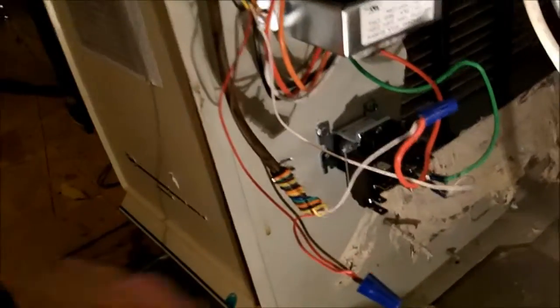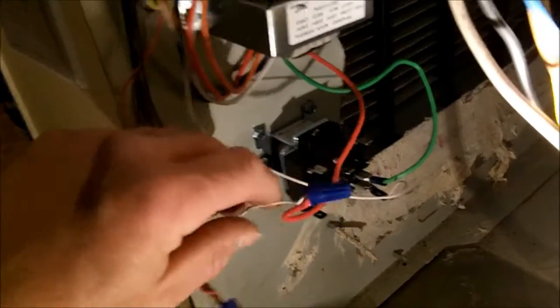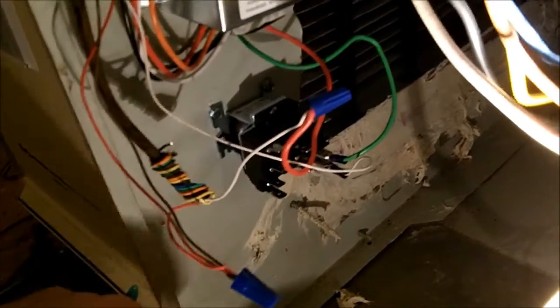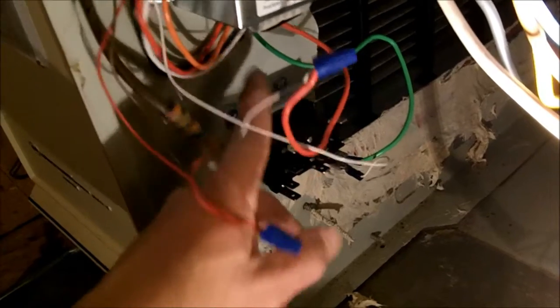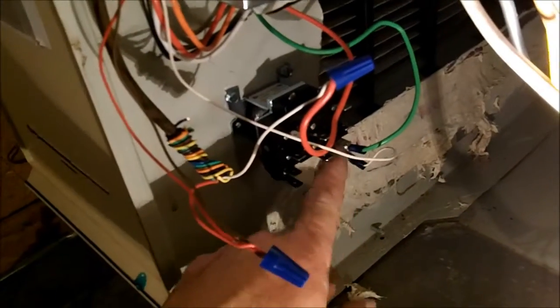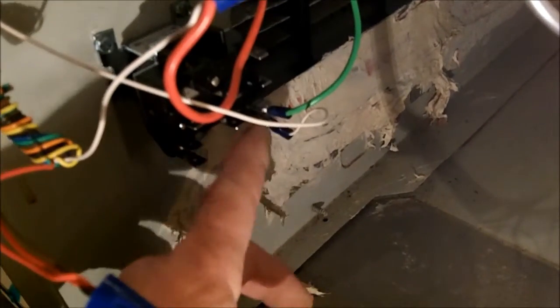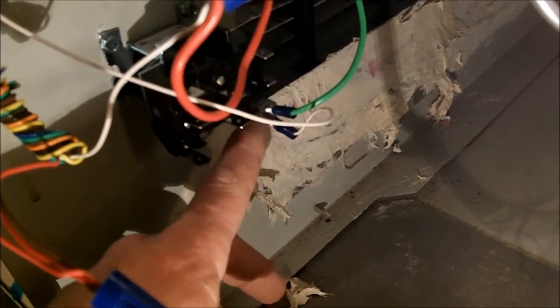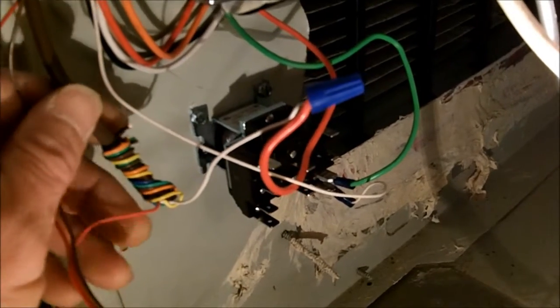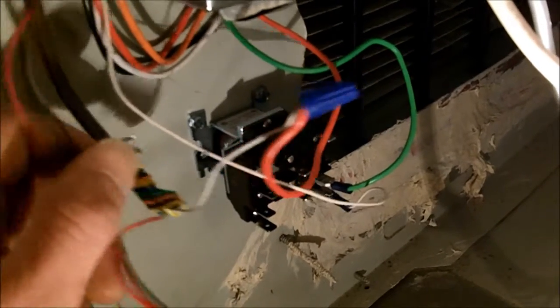Alright, so I got my relay and my transformer mounted. Let me go through it starting off. I've got my common wire coming from the transformer, feeding the common terminal on the coil, and then I use the other terminal to feed my common on my humidistat. I'll need another one for the humidifier, but that comes in a minute.